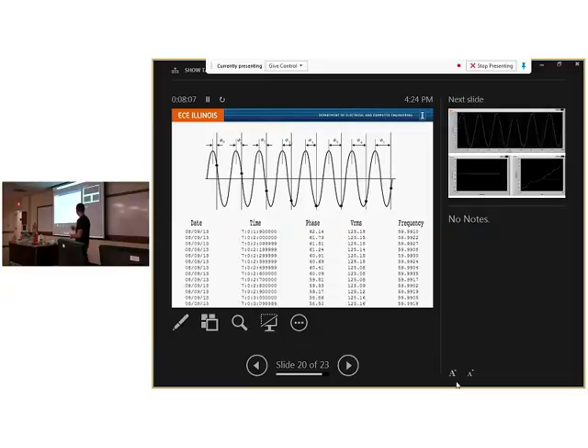This is the data that we get. We see that in our case the frequency is lower than 60 hertz, which means the phase should be decreasing, and it actually does. We also see 10 lines of data per second, as expected. It's interesting that the voltage is 125 volts RMS as opposed to 120, but the national code allows between 114 and 126 volts, so it's within that range.